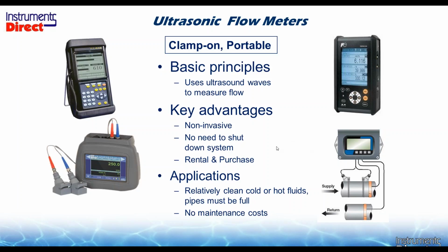So the value of using a transit time flow meter: no holes in the pipe, so you don't have to shut down the process to put in your paddle wheel. You just clamp it on the outside of the pipe. Remove the insulation, put it on the pipe, and cover back up if you like. You can get them readily available online or through different manufacturers. You can buy them and you can rent them.